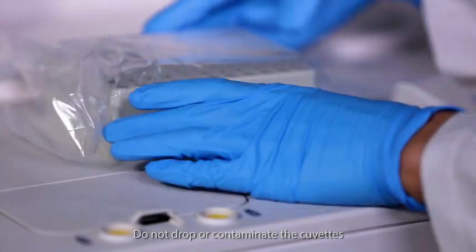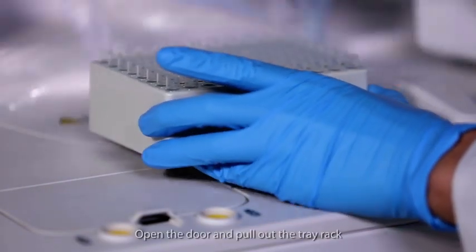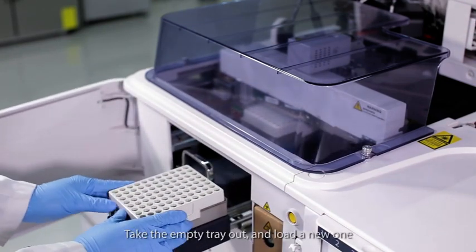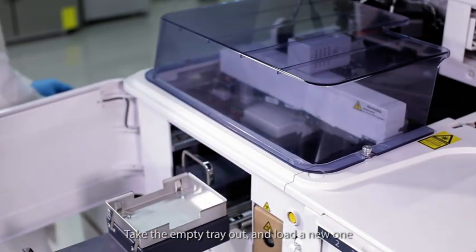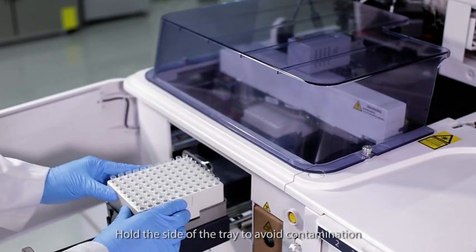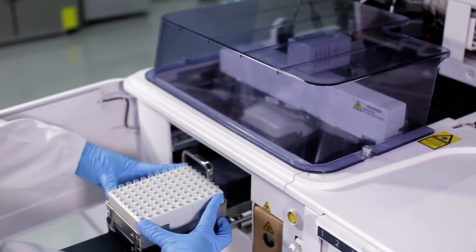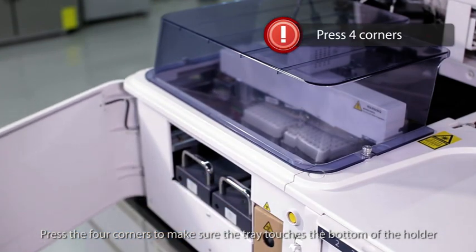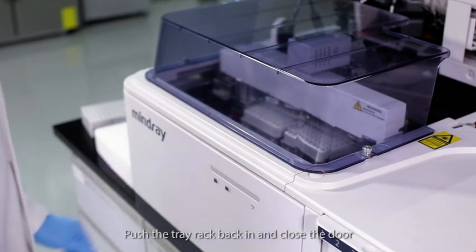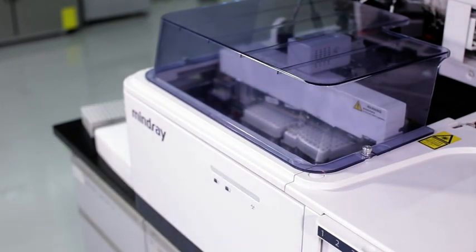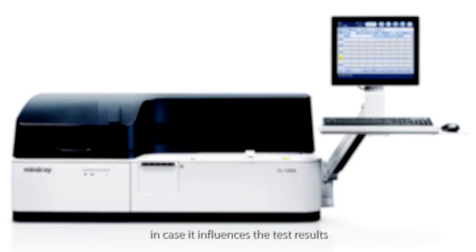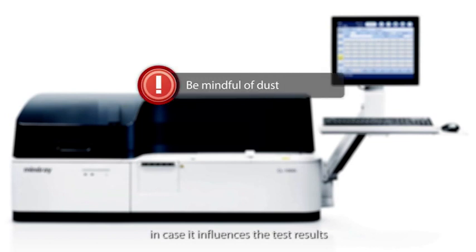Open the door and pull out the tray rack. Take the empty tray out and load a new one. Hold the side of the tray to avoid contamination. Press the four corners to make sure the tray touches the bottom of the holder. Push the tray rack back in and close the door. The software can automatically refresh the number of remaining cuvettes. Be mindful of dust in case it influences the test results.